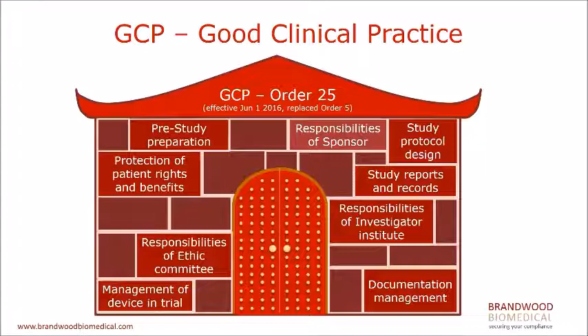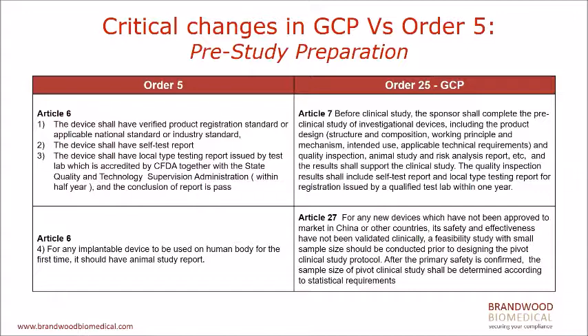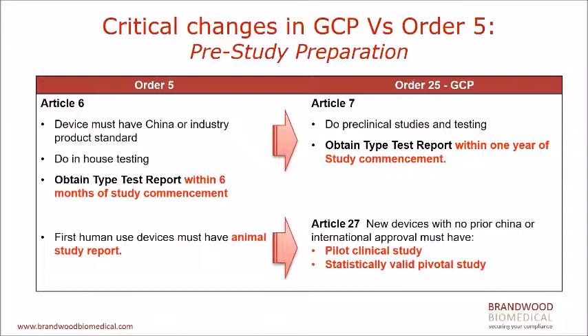So what are the main changes brought by GCP compared with the old Order 5? Here we provide you both the full text to read later and a key points summary for easy reading now. First of all, in the past, the clinical study needed to start within half a year after the local type testing was done. Now you can start within 1 year after the testing is done. And second, for brand new devices, the GCP asks for a pilot study with a comparatively smaller sample size before the statistically valid pivotal study. In the past, Order 5 only asked for an animal study for new implantable devices. No pilot study was required.